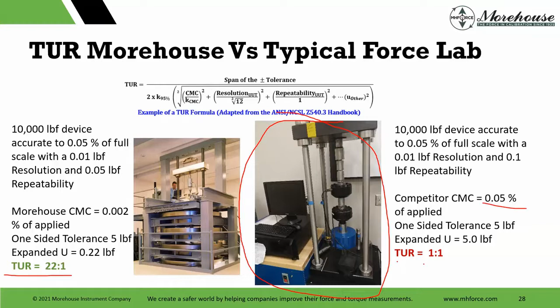So I have a 10,000 pound device. One, I'm using dead weights, and the other, I'm using this transfer machine with a load cell calibrated by dead weights. So on one hand, I have a TUR of 22:1, and on another hand, I have a TUR of 1:1, and that's using this formula. So if I think about those two machines and I do this graphically, it's what it looks like, right? Car example that people saw earlier. Remember the car that could easily fit into the space right here versus not fitting in too well, right?